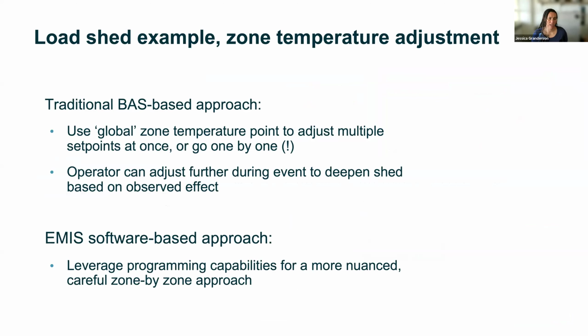Without smart building software, using the BAS, we might find a global point that we could adjust all at once, or we might go one by one. We might not even do zone temperature adjustment, and might go straight to limiting strategies. The operator can be a participant in making temperature adjustments more aggressive through the duration of a flexibility event, if they'd like. In the more full-featured software-based approach, we can leverage more extensive programming capabilities, and follow a more nuanced zone-by-zone approach to these adjustments.